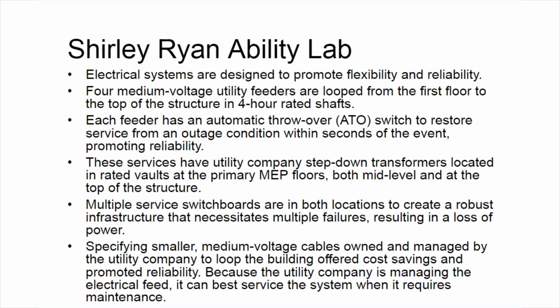The service switchboards in both locations create a robust infrastructure. We've got double-ended switchboards for all the life safety and critical loads. And we have medium voltage cables that are owned by the utility company, so the owner doesn't have to manage them.